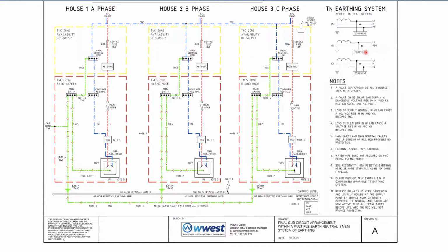Then you've got type C, which is TNCS, and this is the common one that we use in Australia. The TNCS uses the line active, then you've got your neutral, and off that you've got your protective earth as a combined and a separate. There's the combined coming down to the equipment. Now that goes all the way to the equipment. Then you've got your separate earth coming across here as a separate earth down to the equipment as well, and there you've got the active.